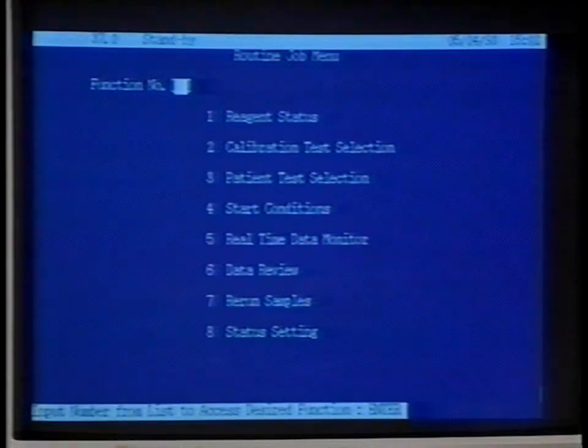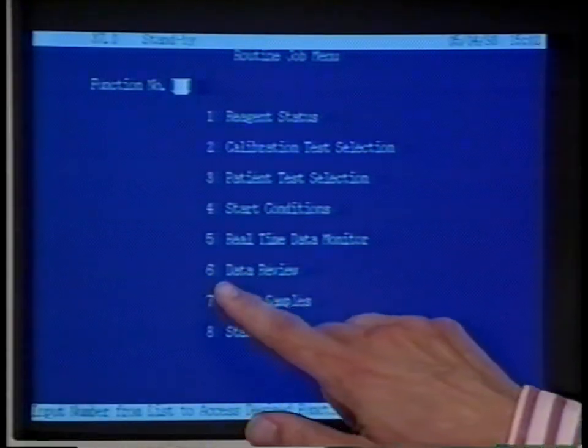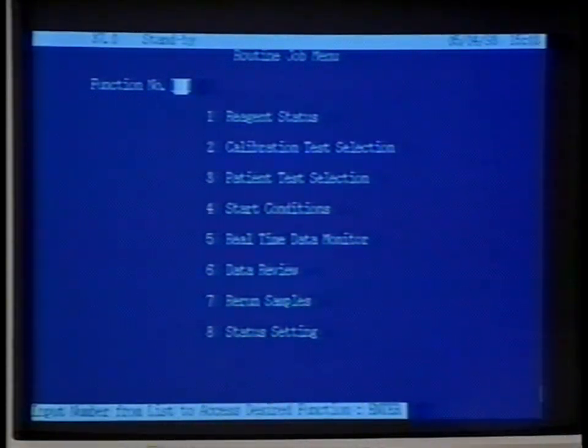Another screen, the Data Review screen, allows reviewing and editing of patient data. It also is used for reprinting reports or retransmitting data to a host computer. Some of this can even be done during operation. The Rerun Sample screen allows you to view or edit samples to be rerun. The Status Settings screen is used to program the analyzer to automatically perform daily startup tasks at a pre-programmed time. You don't even need to be in the laboratory.